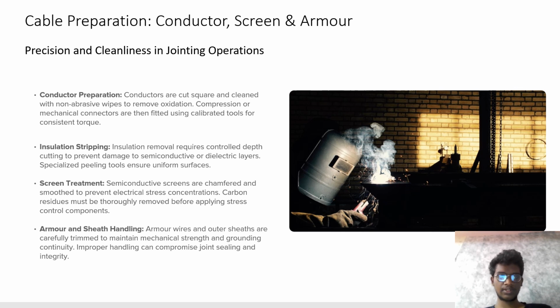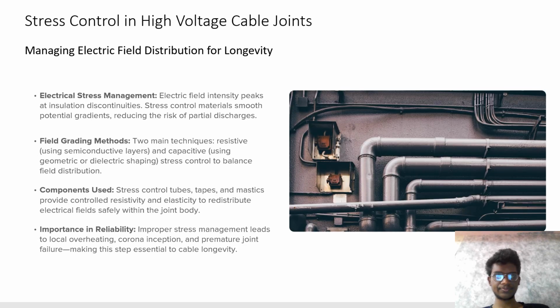Screen treatment: semiconductor screens are trimmed and smooth to prevent dielectric stress concentration. Carbon residues must be thoroughly removed before applying stress control components. Armor and sheath handling: armor wire and the outer sheath are carefully removed to maintain mechanical strength and grounding integrity. Improper handling can compromise joint sealing and integrity.